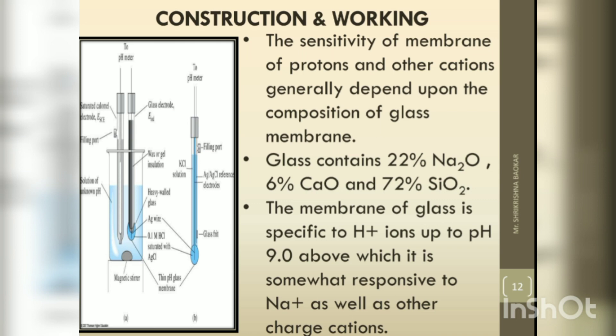Glass contains 22% of Na2O (sodium oxide), 6% CaO (calcium oxide), and 72% of SiO2 (silicon dioxide). The membrane of glass is specific to H+ ions up to pH 9, above which it becomes somewhat responsive to Na+ as well as other charged cations.